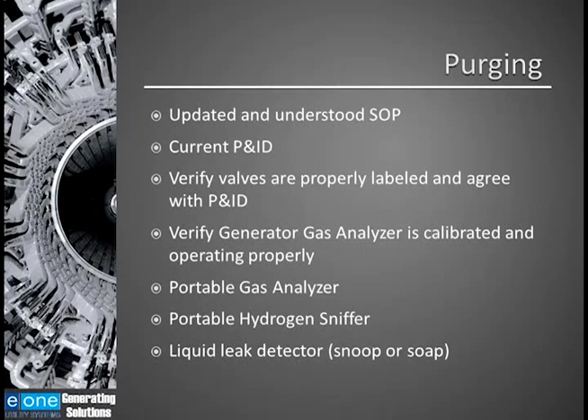The next two items are very important because the valves on these gas manifolds are not exercised that often. In many cases, generators can go 5-10 years without being purged. So these valves are not being used, and the packing in the valves may become stiff or brittle, and when they are used, they might leak. So I think it's very important that you have a portable hydrogen sniffer available during the purging process. If you do not have this, at a minimum, I believe you should have a liquid leak detector, snoop or soap, available to look for leaks.